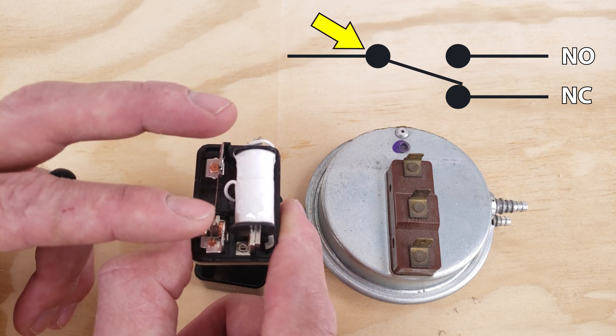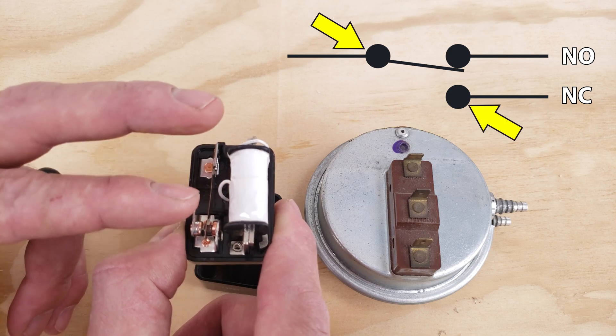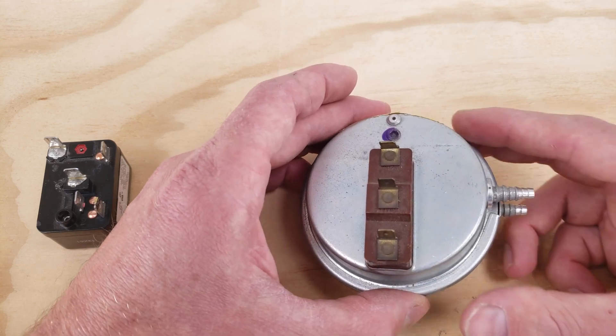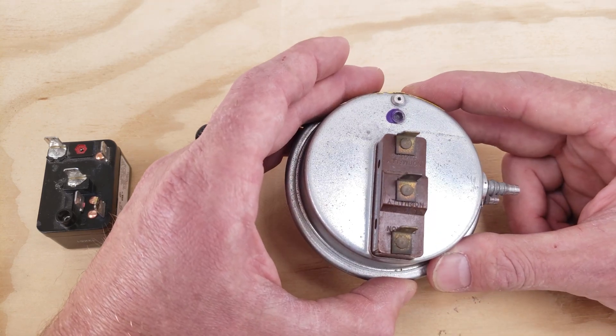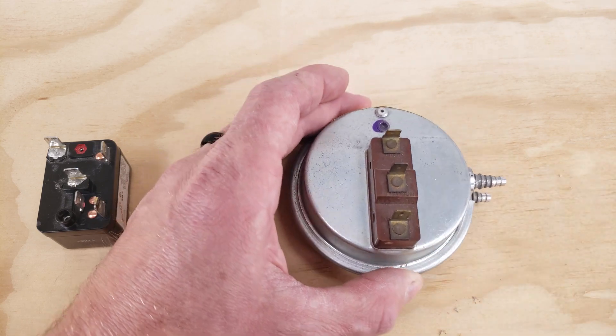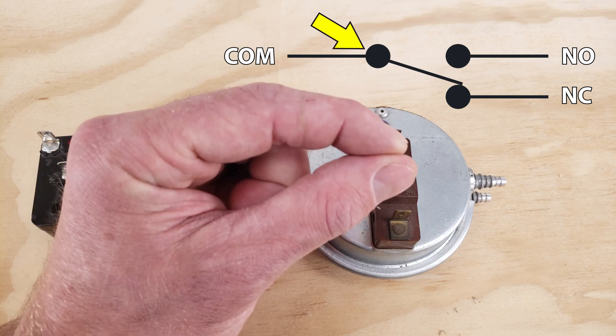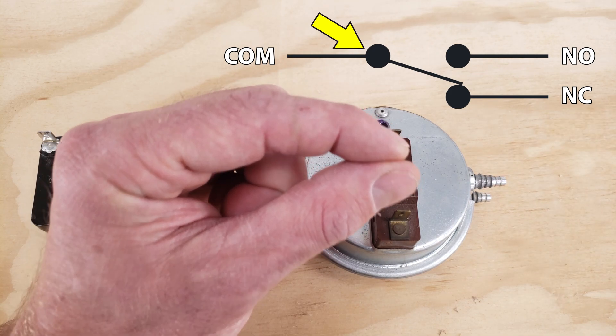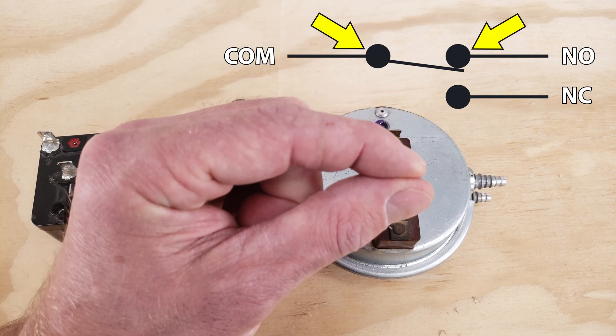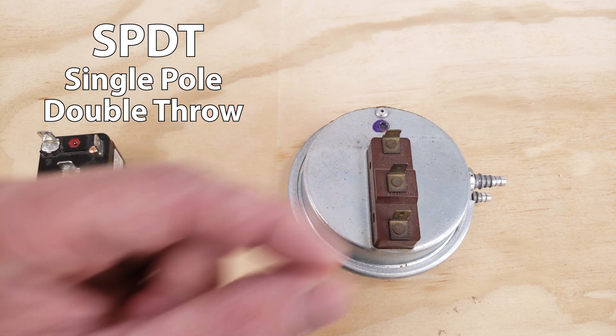You'd have one set of normally closed contacts and one set of normally open contacts. When you power the coil, the normally open contacts are going to close and the normally closed contacts are going to open. Then you have a pressure switch here — since this has three tabs you have a common connection point, a set of normally open contacts, and a set of normally closed contacts. When you activate the switch by lowering the pressure you're going to open the normally closed contacts and close the normally open contacts. So this is a SPDT — single pole double throw switch.